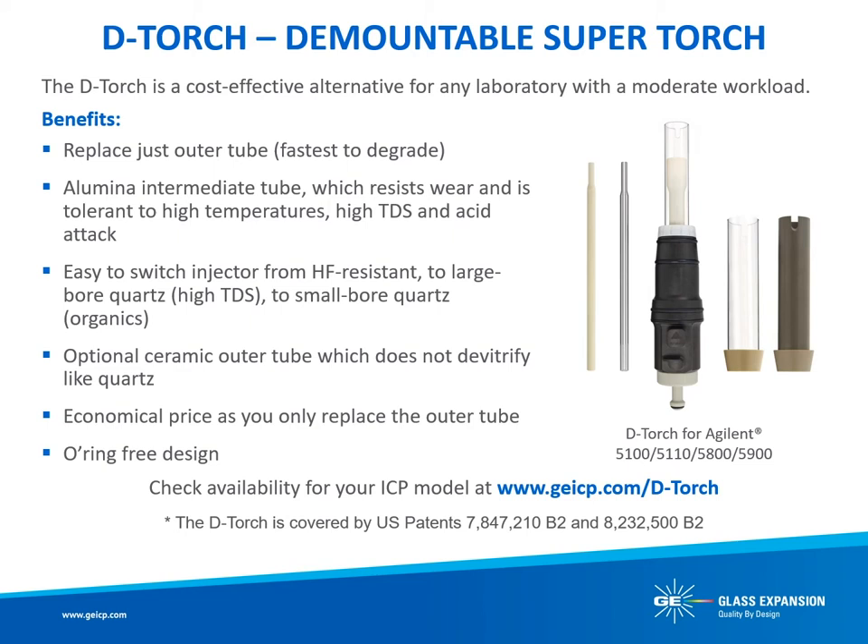Glass Expansion's patented D-Torch is an economical alternative to the single-piece and other semidemountable torch options. The D-Torch, often referred to as a supertorch by our customers, incorporates a ceramic intermediate tube for greater robustness and provides the analyst with an outer tube that can be replaced when it fails rather than replacing the entire torch. The D-Torch also features an interchangeable injector, allowing the analyst to install a specific injector — whether it be for material or internal diameter — for each application, such as aqueous, organics, high total dissolved solids, or hydrofluoric acid. Each Glass Expansion D-Torch design is a direct replacement for the standard torch, including ICP models that incorporate an easy-to-use, self-aligning torch installation.